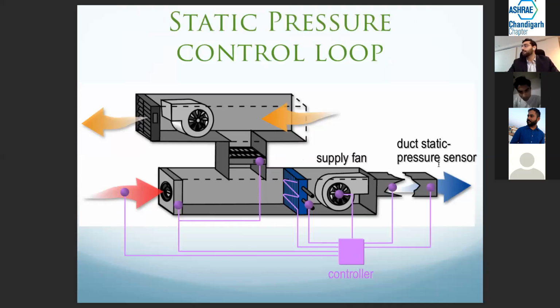Static pressure. So now we've added a duct static pressure sensor. We want to make sure that if the air handler is serving VAV boxes, for example, and the VAV boxes are closed, the duct doesn't blow. So we want to put in a duct static pressure sensor to keep a check on that at all points in time. Now you see there's a controller and a supply fan. If there's too much static pressure in the duct, the controller can tell the supply fan to turn the speed down, assuming it has a VFD, and make sure that this duct static pressure sensor reading is where we want it to be.